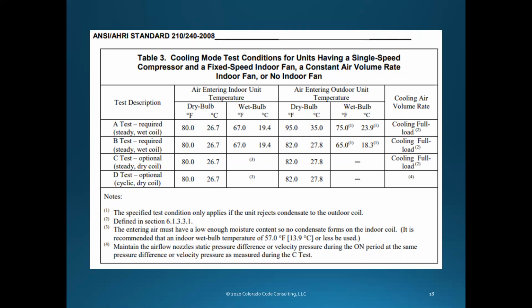The bad thing is it's not always what you're designing to. Take this test here: it's saying the entering dry bulb temperature—remember we talked about that last week, the sling psychrometer, the difference between wet bulb and dry bulb. So the dry bulb is 80, the wet bulb is 67, and it's saying the outdoor entering temperature—the compressor sitting outside the building—the air entering it is 95 degrees.